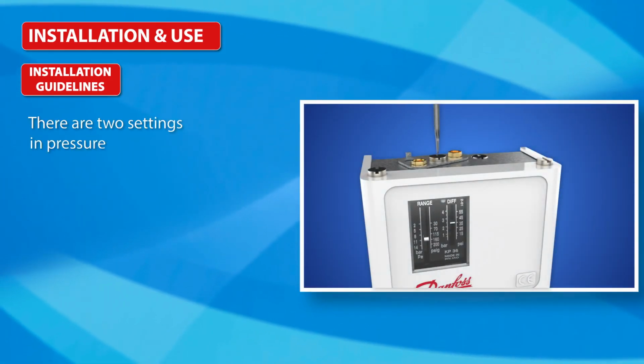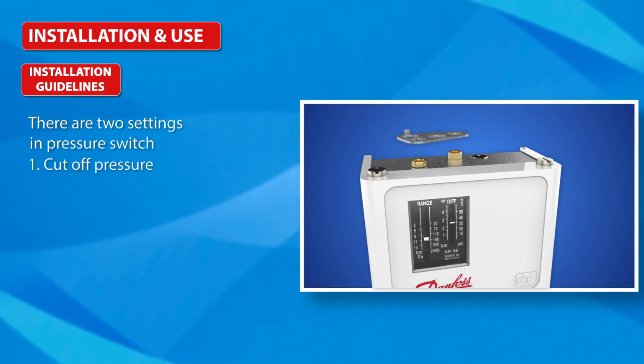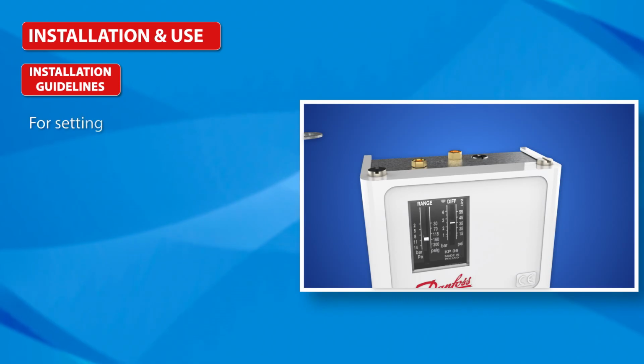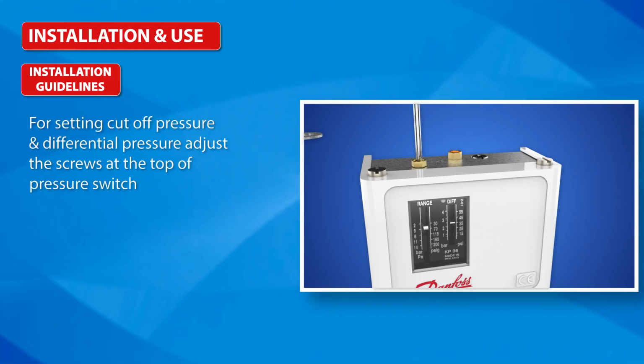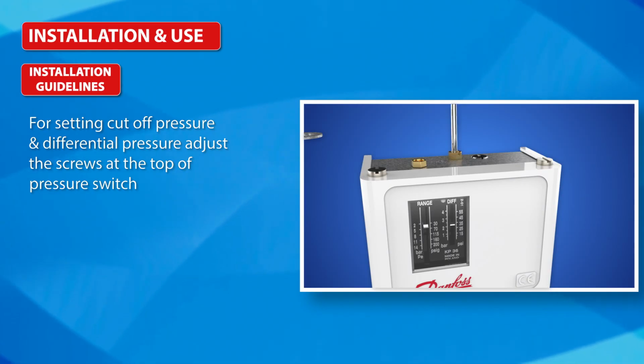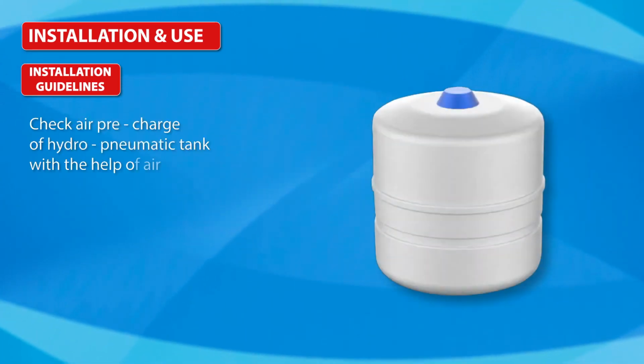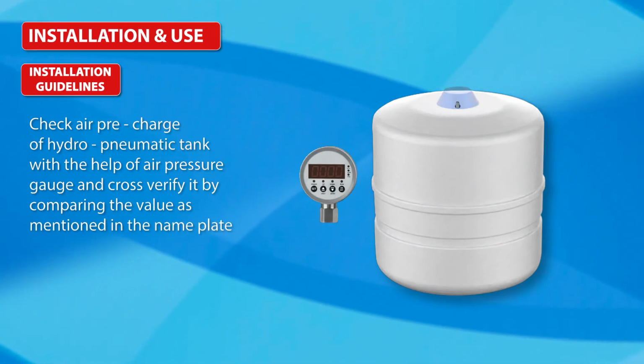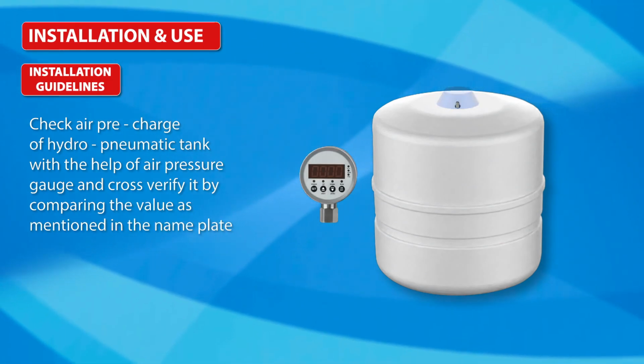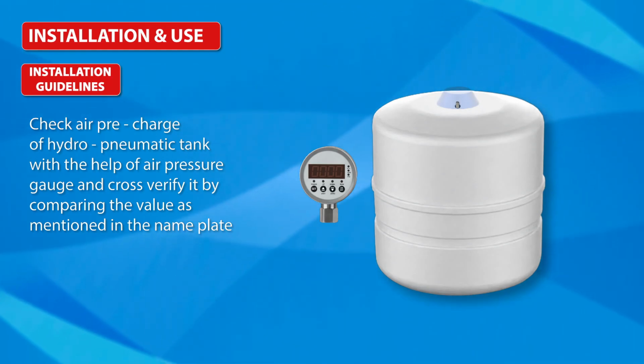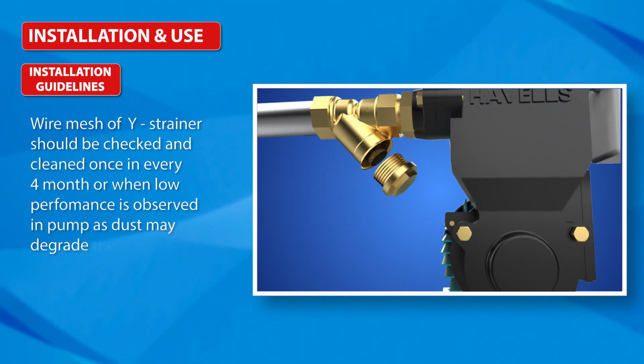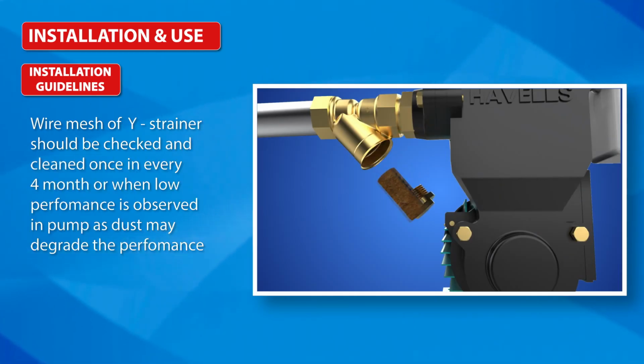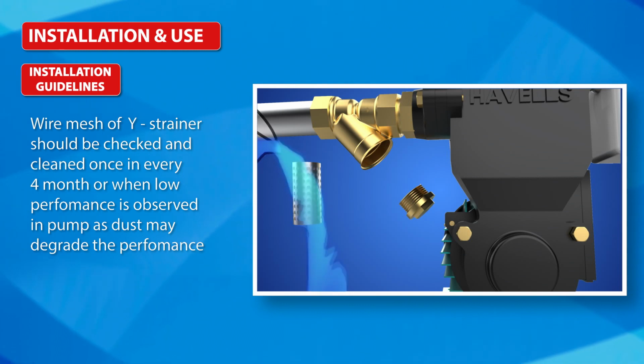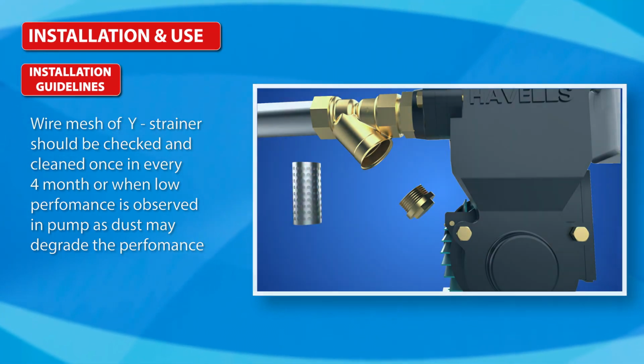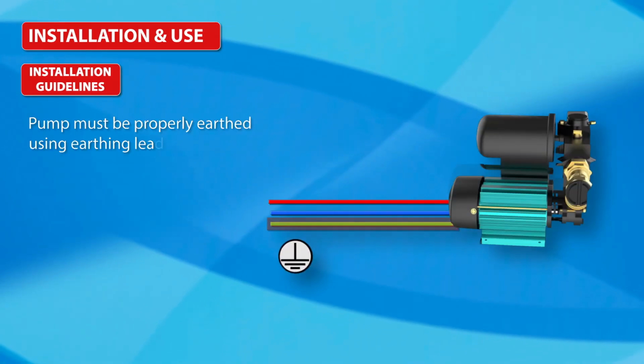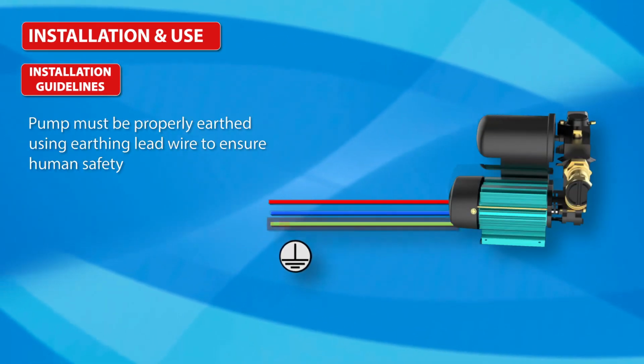There are two settings in the pressure switch. First, cut-off pressure. Second, differential pressure scale. For setting cut-off pressure and differential pressure, adjust the screws at the top of the pressure switch. Check the air pre-charge of the hydro-pneumatic tank with the help of an air pressure gauge and cross-verify it by comparing the value mentioned on the nameplate. The wire mesh of the Y strainer should be checked and cleaned once every 4 months or when low performance is observed in the pump, as dust may degrade performance. The pump must be properly earthed using an earthing lead wire to ensure human safety.